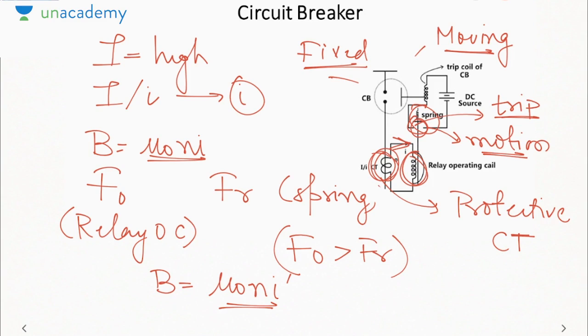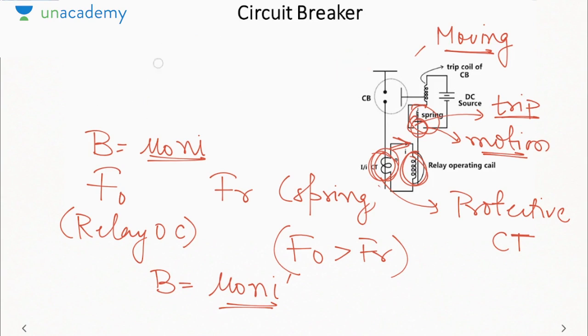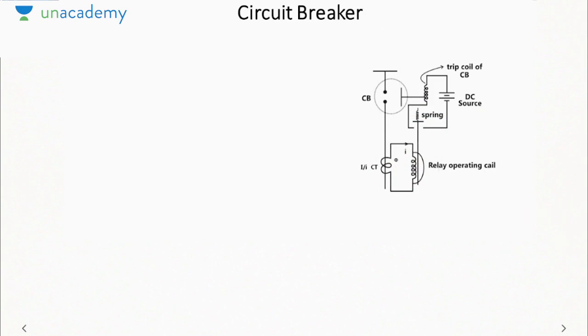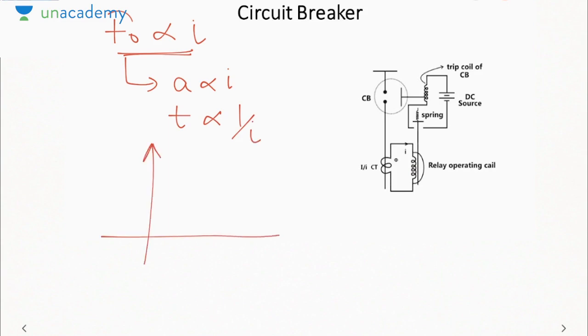Now what is the essential difference between the two types of transformer? What I want is that the operating force must be directly proportional to current. Why? Because if the operating force is directly proportional to current, then acceleration is directly proportional to current, then operating time is inversely proportional to current. So what happens is, the higher the current, the lesser will be the time. That means a higher current will exist only for a shorter duration in my circuit. So that is why I want the time to be inversely proportional to current.